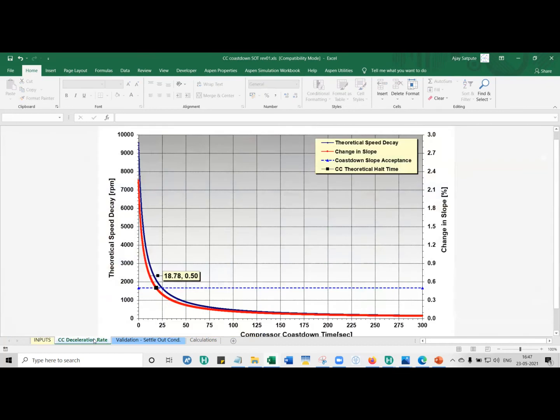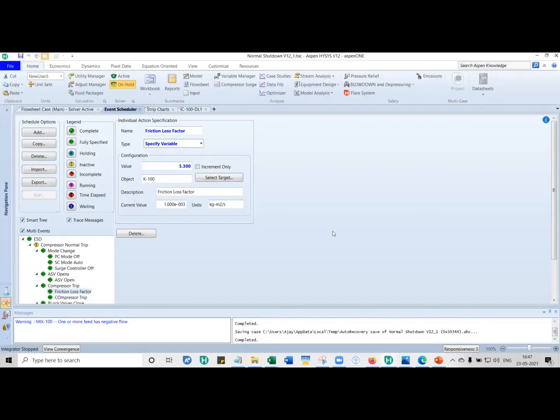Based on that, the idea is to impose this drop in speed into HYSYS. So what we can do is use a friction loss factor. Now this is trial and error. In my case, I started with 1, 1.5, 2, 2.5, until I came to 5, then I kept playing around with the number and I put 5.3.